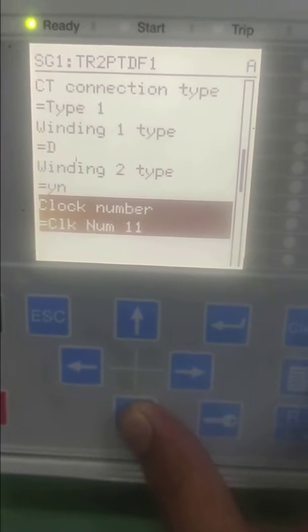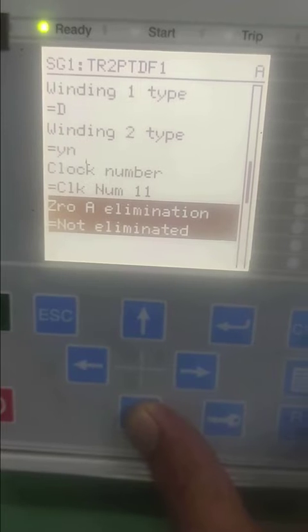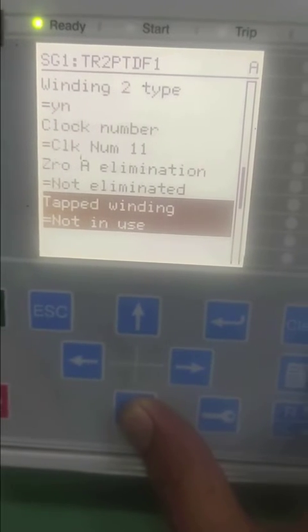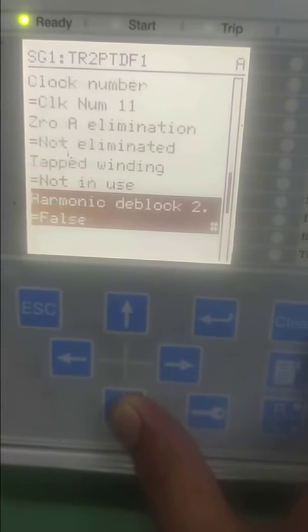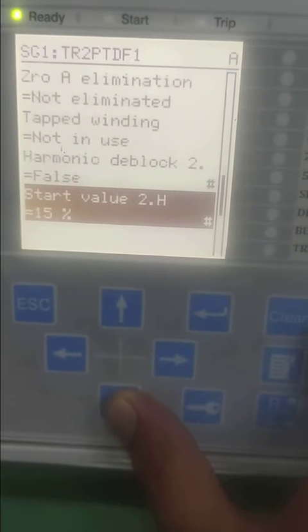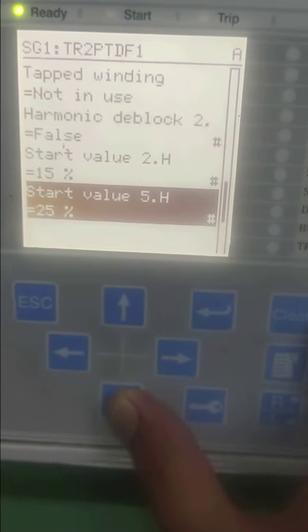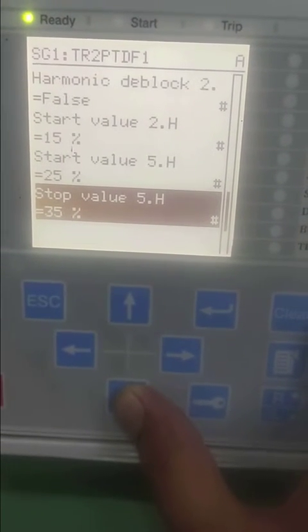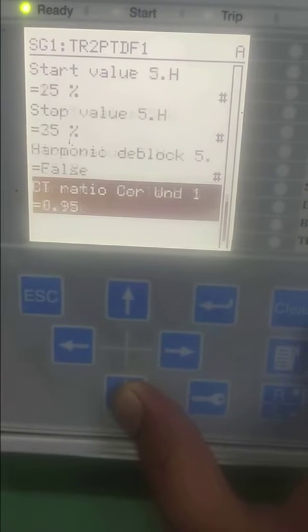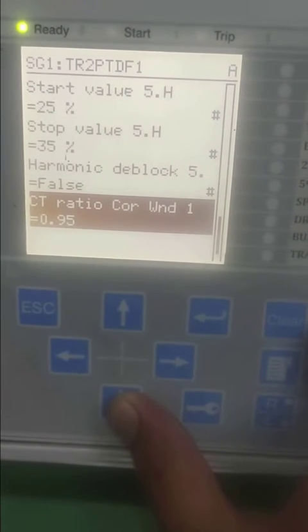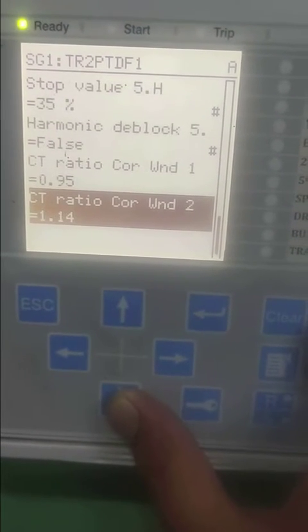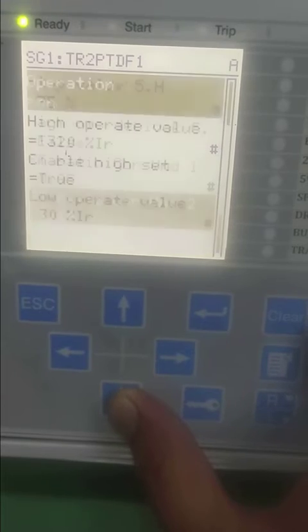Accordingly you have to select winding one type and winding two type. If you have star-star winding or star-delta winding, you need to determine whether zero sequence elimination is required or not required. According to the manual, zero sequence is not required for star-delta-star configuration.